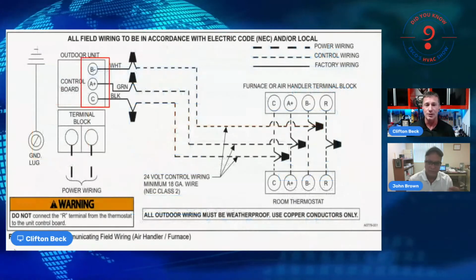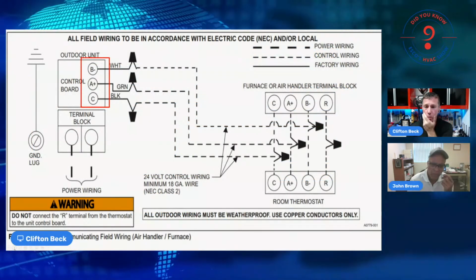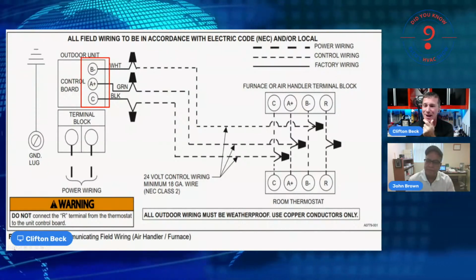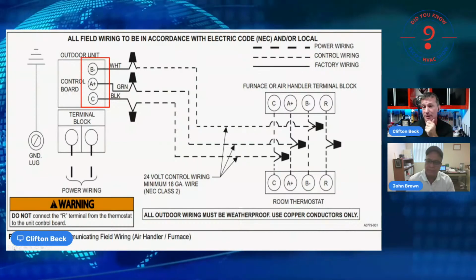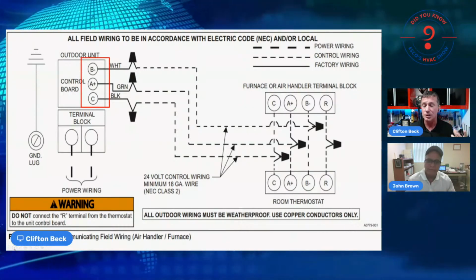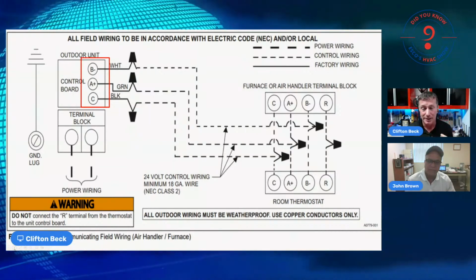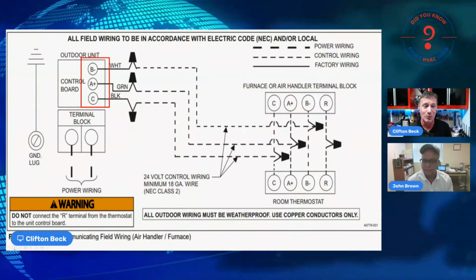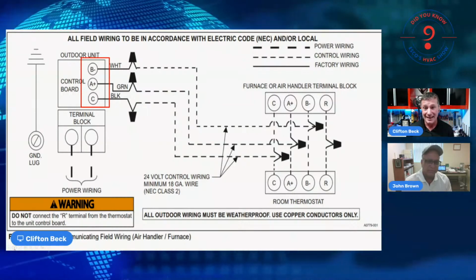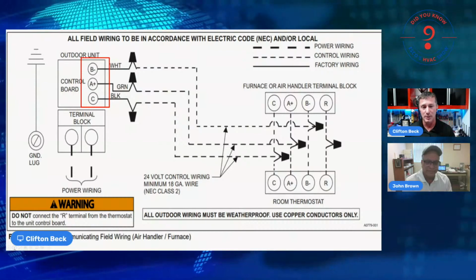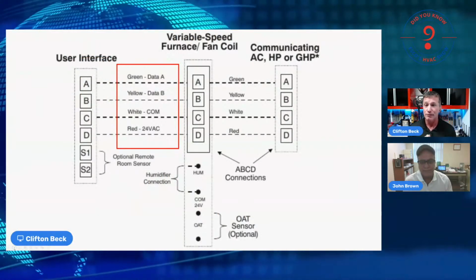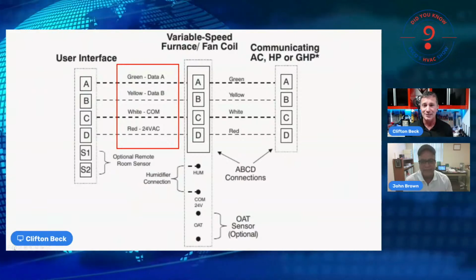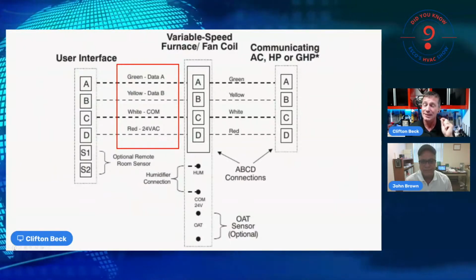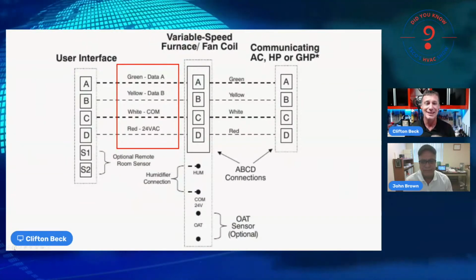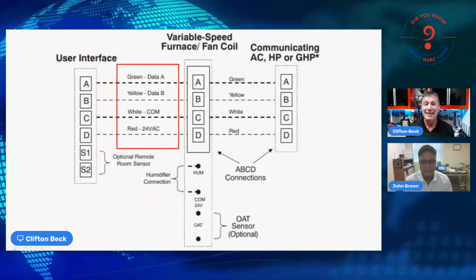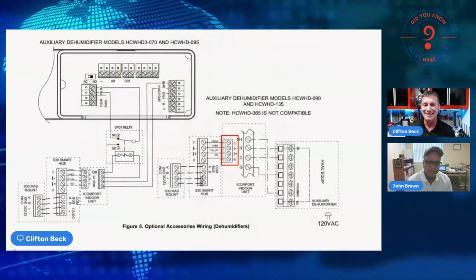Let's look at another manufacturer. Looking at this wiring diagram, I see another positive and negative signal, using a common as a ground reference point. This manufacturer uses 3 wires: a grounded common, which is our ground reference point, a positive signal on A in reference to ground, and a negative signal on B in reference to ground. With this next manufacturer, they're also using a 4-wire connection, but you'll notice they use common and 24 volts AC for the load on the controller, and data A and data B, which happen to be our DC communicating signal.